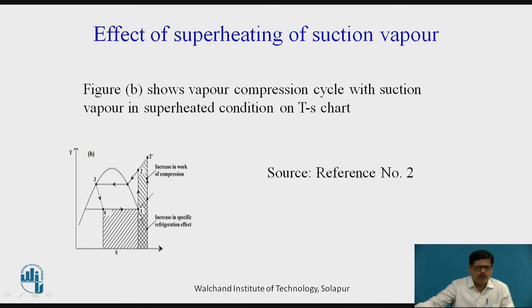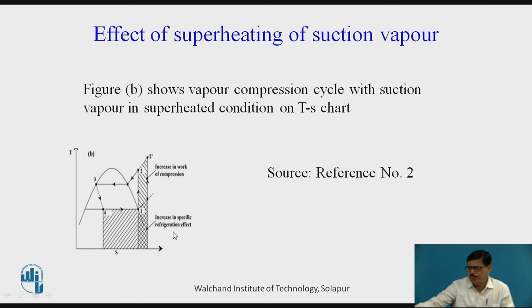Whenever we consider that the initial vapor is superheated, then point 1 will be shifting towards the higher side. The temperature of the vapor entering the compressor will be superheated — greater than T1, maybe T1 dash. So 1 dash, 2 dash will be the compression with suction vapor superheated. The hatched area shown on the right-hand side represents the refrigerating effect for the superheated case.